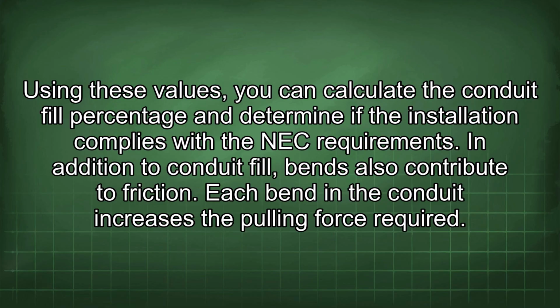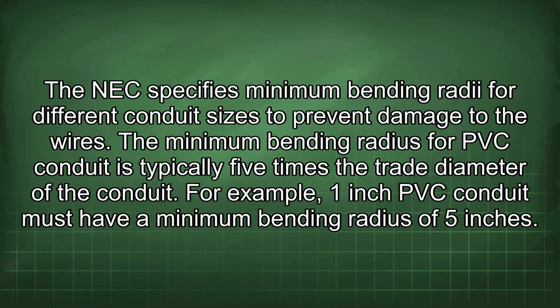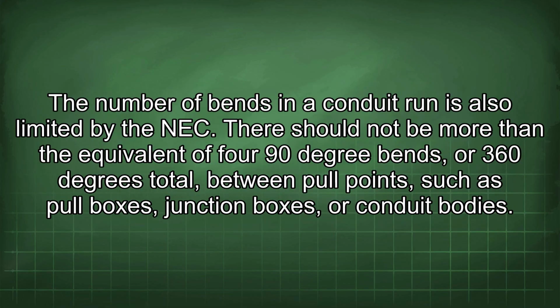In addition to conduit fill, bends also contribute to friction. Each bend in the conduit increases the pulling force required. The NEC specifies minimum bending radii for different conduit sizes to prevent damage to the wires. The minimum bending radius for PVC conduit is typically 5 times the trade diameter of the conduit. For example, 1-inch PVC conduit must have a minimum bending radius of 5 inches. The number of bends in a conduit run is also limited by the NEC. There should not be more than the equivalent of 4 90-degree bends, or 360 degrees total, between pull points such as pull boxes, junction boxes, or conduit bodies.